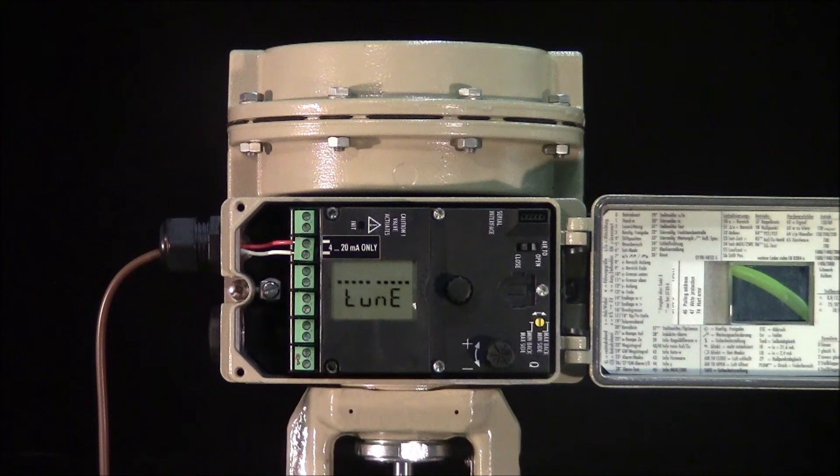Once the calibration is completed, the display will briefly show tune and then revert to the position specified by the control signal. In this case, we've set it to 12 mA or approximately 50% as indicated by the display.